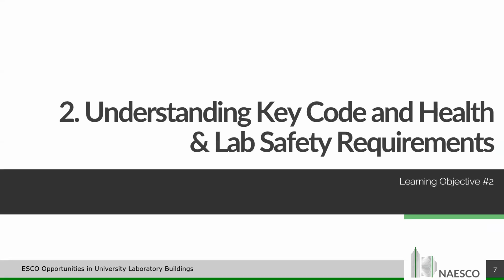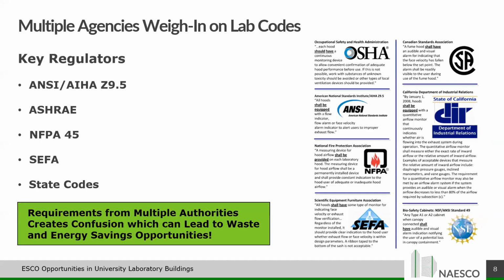Now let's dive into some of the code issues around labs. There's multiple agencies that weigh in when it comes to design code and operating code for labs. ANSI Z9.5 is probably the chief code, but ASHRAE dips in, so does NFPA 45. You've got a variety of state codes, depending on where you're working, that you need to think about. And these codes aren't written black and white, they're a little bit gray. So it generates this conservative nature when it comes to labs. Like I said, a lot of the designs are done conservatively, and there's a lot of waste, which creates opportunity.